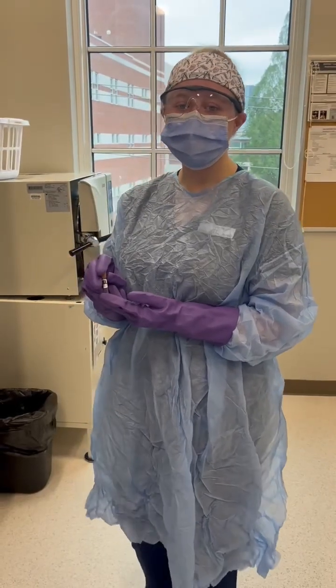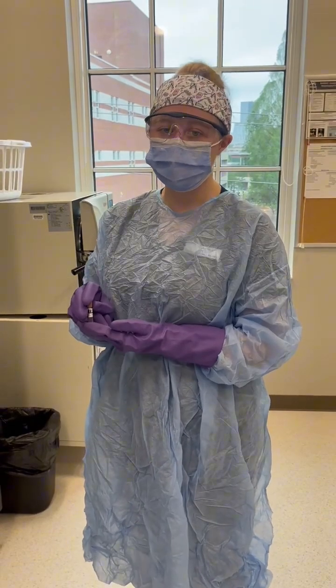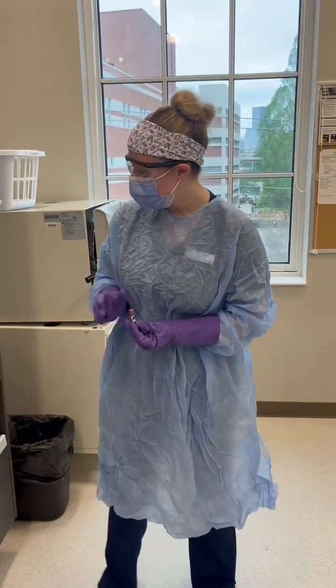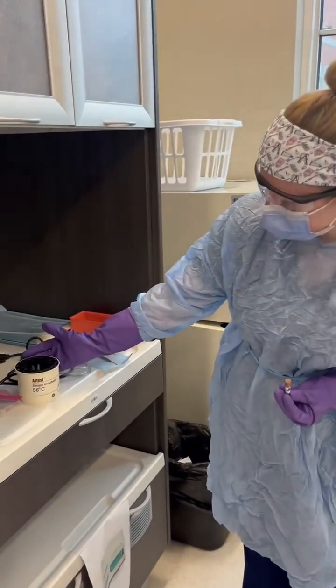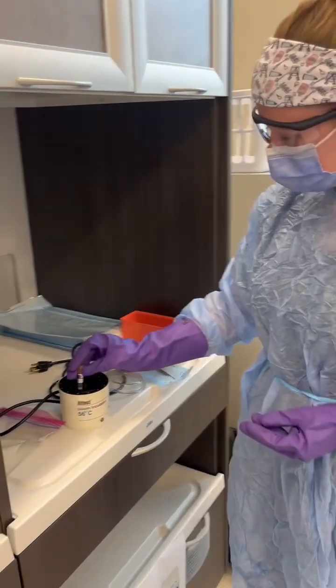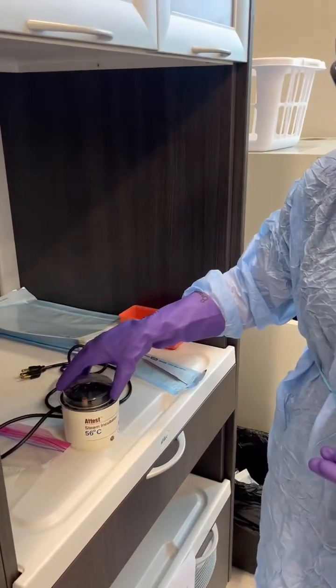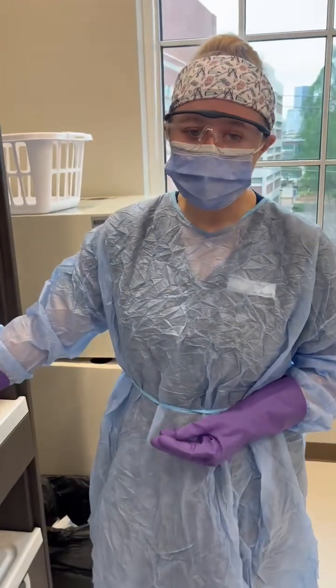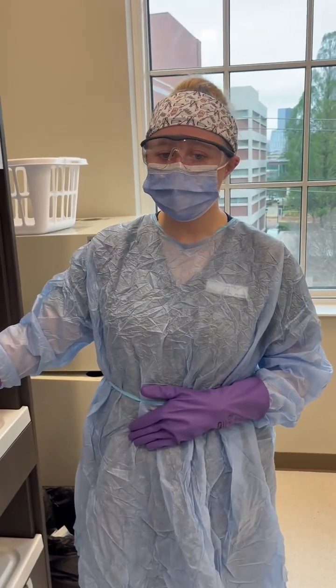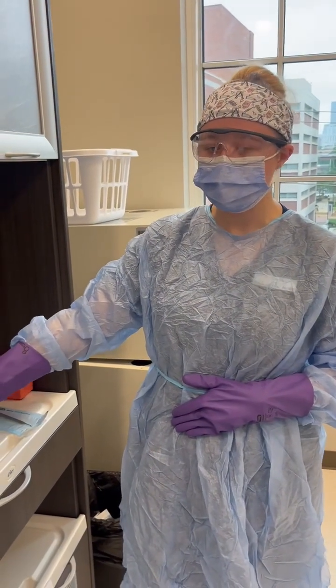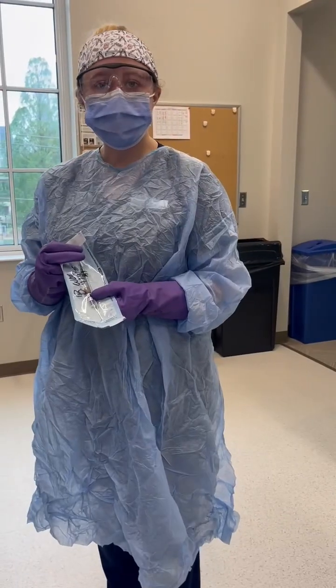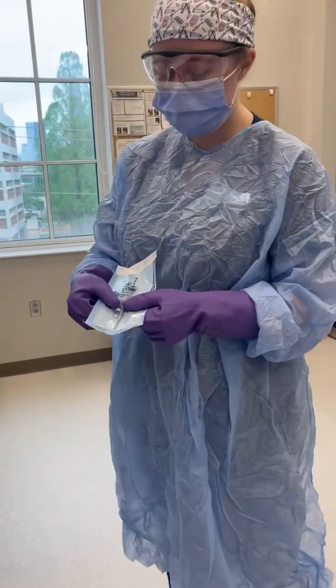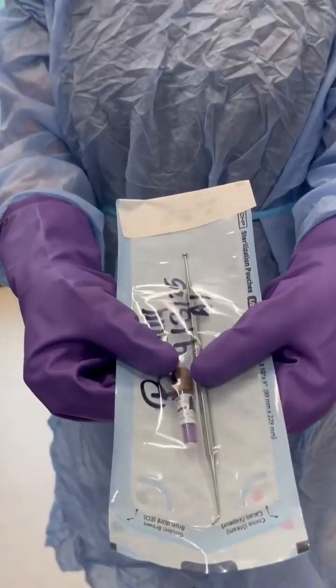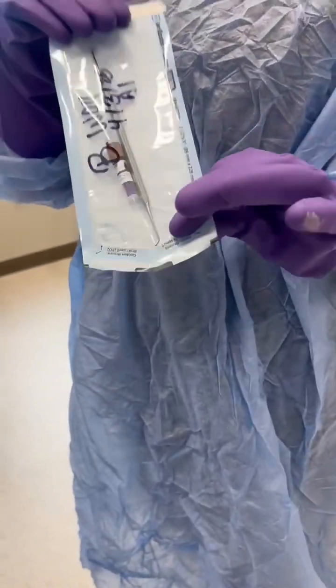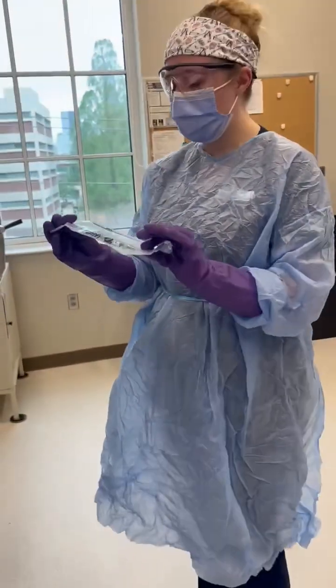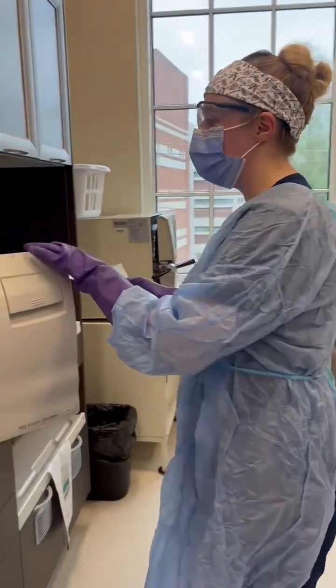The next process is to crush the capsules for biological monitoring. For us, we have this steam incubator, so you would just put that in there and put the lid on, and the capsules will open so that the biological indicator inside can be exposed to the sterilization process. After writing all the necessary information on the indicator, you would place it in a bag with its instrument, and you would put the bag inside the autoclave.